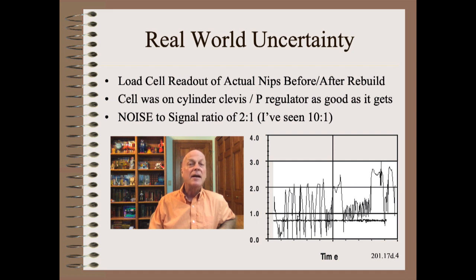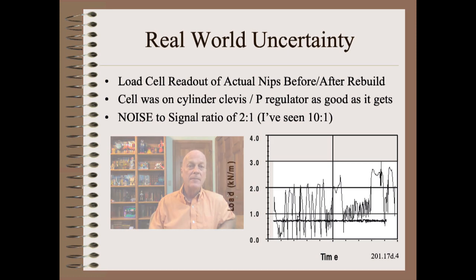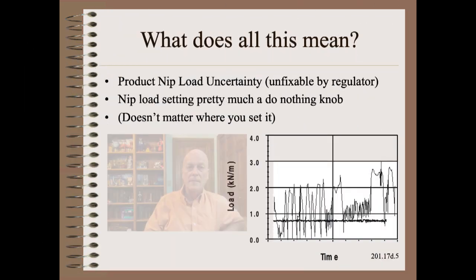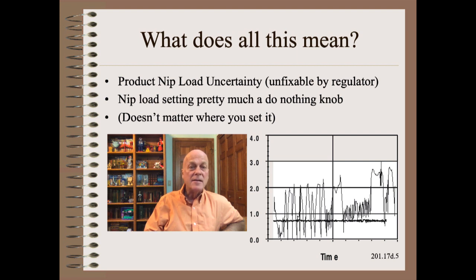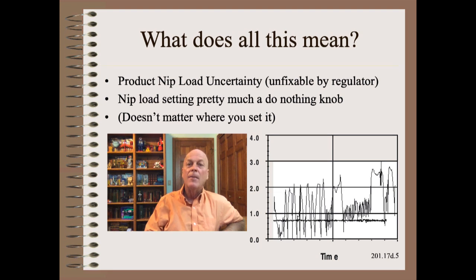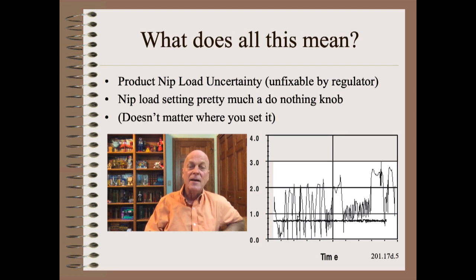However, it can get much worse. I worked on an old tissue winder where the nip load uncertainty was ten times the size of the desirable nip load. What this means is that the nip load is quite variable, and that variability is unfixable by getting a better regulator or by adding load cells, at least in the majority of cases. What this means is that the nip load setting is pretty much a do-nothing knob — it doesn't matter much where you set it. The actual nip load on the product will be all over the place.